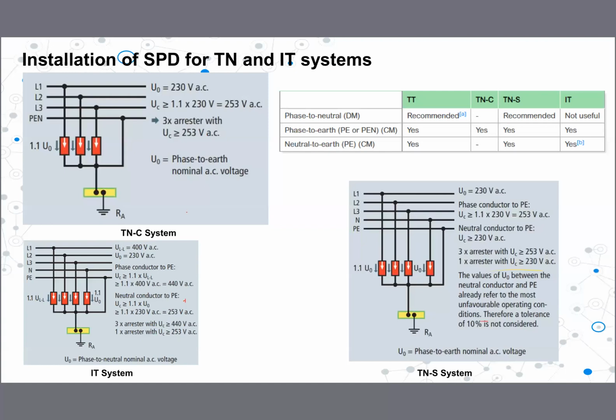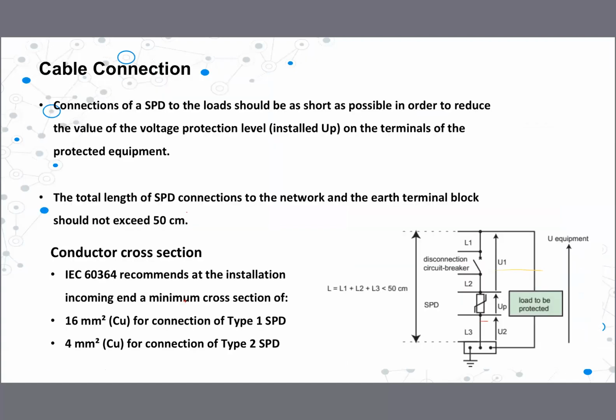And in a TT system also, phase to earth plus neutral to earth, it is mandatory to install, right? So then let's look at what is the correct connection of cable in the SPDs, right? So the connection of SPDs to the load should be as short as possible to reduce the UP value, right? Now here in this diagram, you can see this is the UP, right?